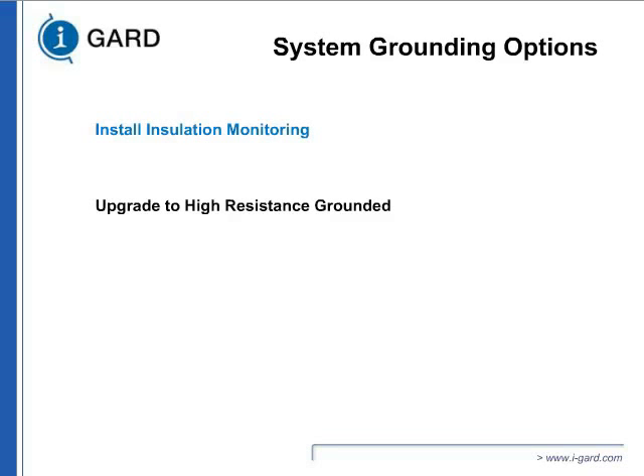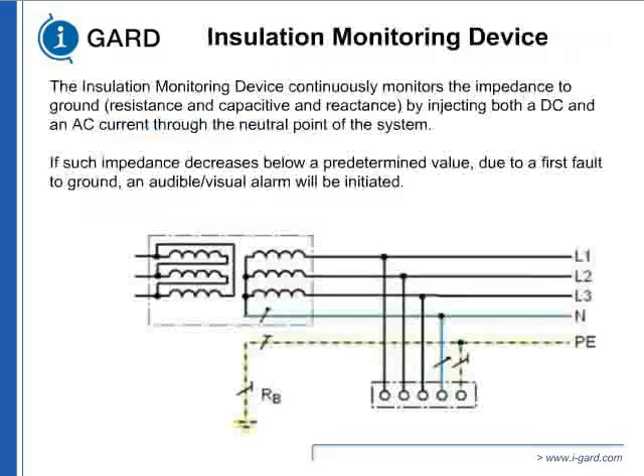How does an insulation monitoring system work? Most of them work offline. Some of them work online. All you do is monitor the impedance of the circuit, and as soon as the insulation starts failing, it can give you a value saying, hey, I am going below a certain value, and you can do something. You can take a planned outage. The basic philosophy in the process industry always was that a planned outage is a lot less expensive and a lot less troublesome than an unplanned outage. So insulation monitoring was the answer.